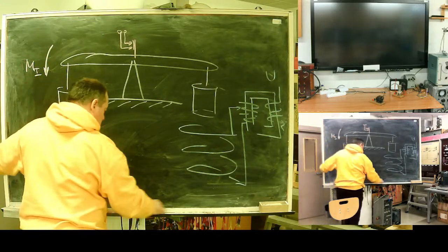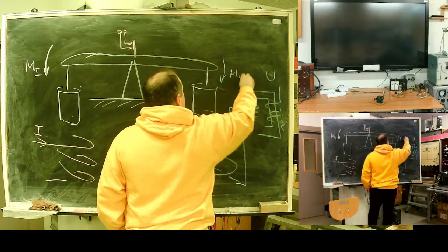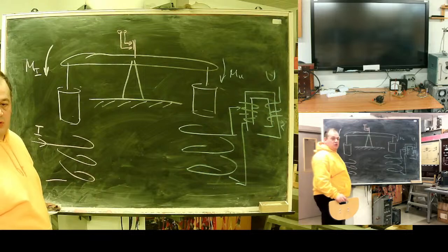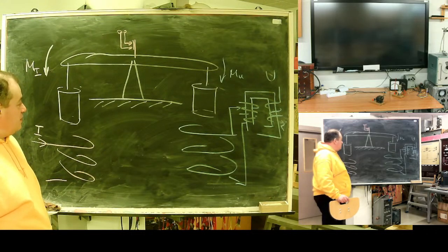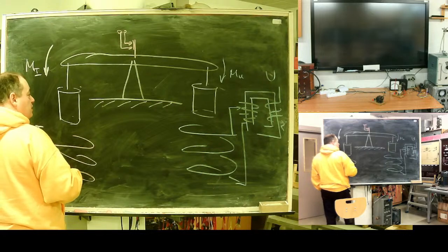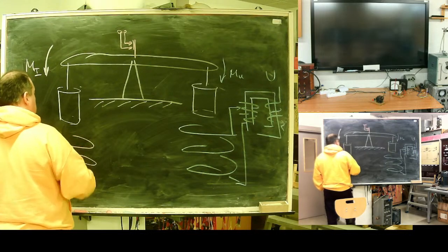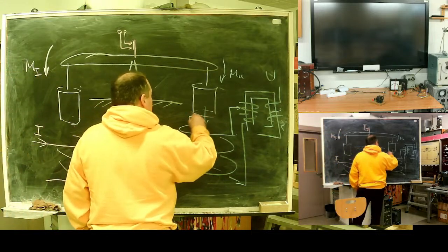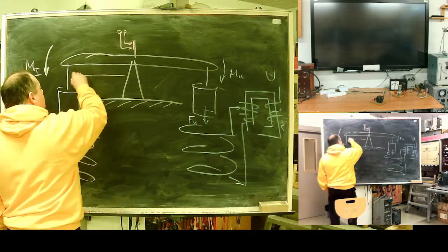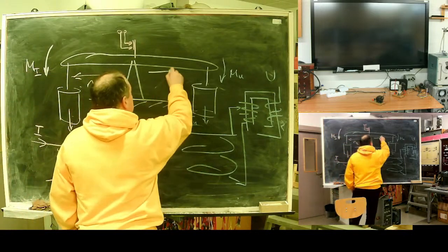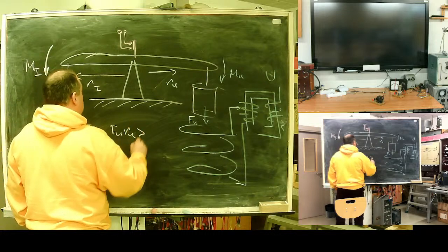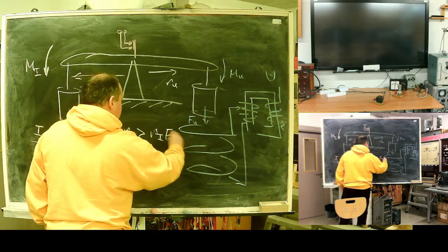So this one is to operate, the current moment; the opposite, the voltage moment, is braking. It's a current balance with an opposing force from the voltage. Force from voltage, force from current, radius for current, radius for voltage. So if FI is higher than FU, the relay will trip.